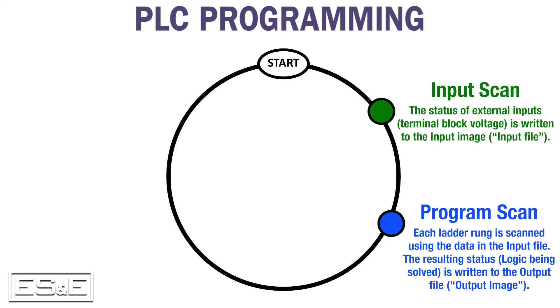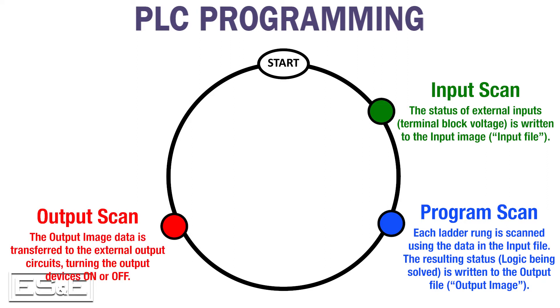Understand that it's updating the output image and not the actual outputs. During the output scan, the output image is transferred to the external output circuits, turning the output devices on and off.